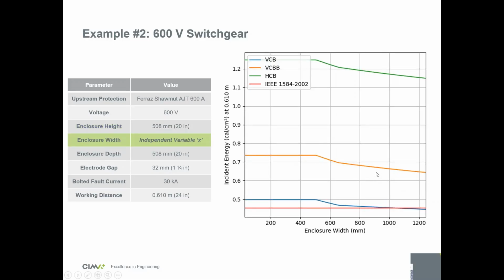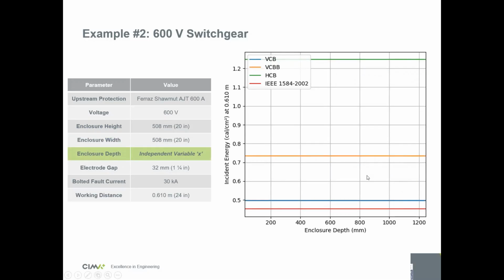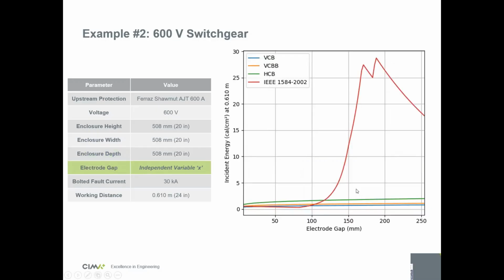Same thing with the width, absolutely the same. And then it's the depth. Well, it cannot be shallow because the voltage is equal to 600 volts. To be shallow, it has to be lower than 600 volts. So in this case, it cannot be shallow. That's why depth has absolutely no impact.